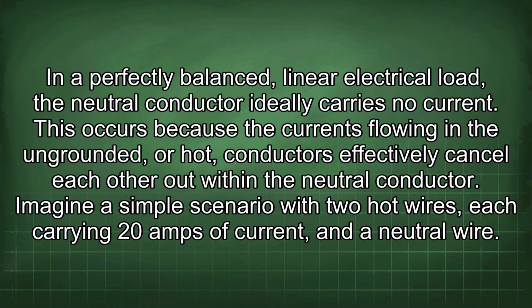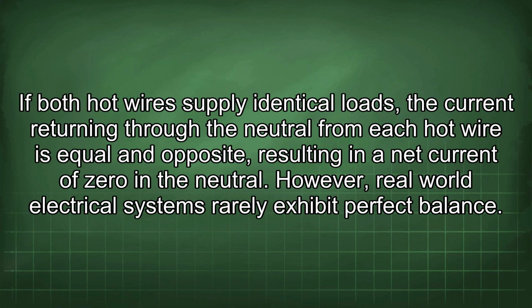In a perfectly balanced linear electrical load, the neutral conductor ideally carries no current. This occurs because the currents flowing in the ungrounded or hot conductors effectively cancel each other out within the neutral conductor. Imagine a simple scenario with two hot wires, each carrying 20 amps of current, and a neutral wire. If both hot wires supply identical loads, the current returning through the neutral from each hot wire is equal and opposite, resulting in a net current of zero in the neutral.